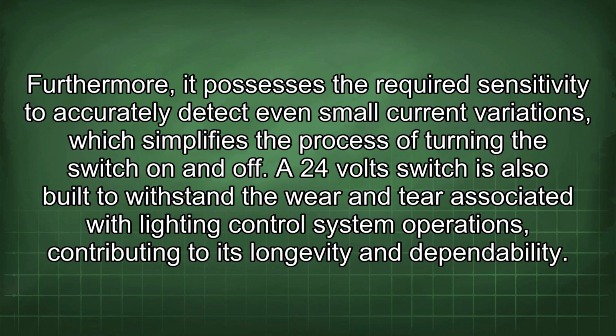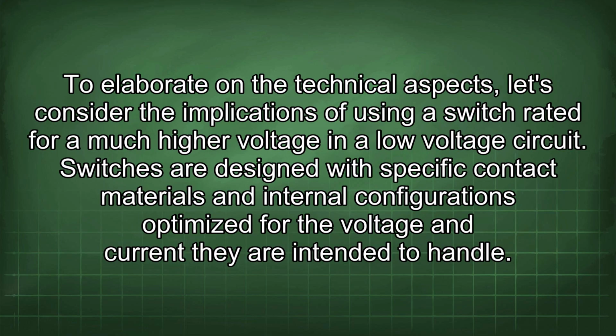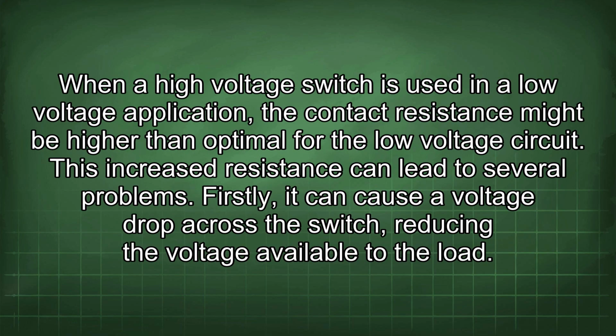contributing to its longevity and dependability. To elaborate on the technical aspects, let's consider the implications of using a switch rated for a much higher voltage in a low voltage circuit. Switches are designed with specific contact materials and internal configurations optimized for the voltage and current they are intended to handle. When a high voltage switch is used in a low voltage application, the contact resistance might be higher than optimal for the low voltage circuit. This increased resistance can lead to several problems.